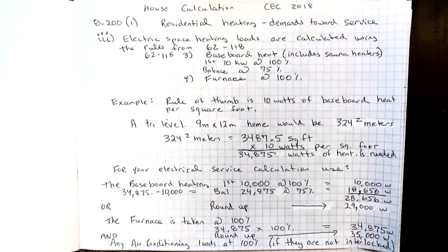Section 4 says that for a furnace, we have to take that as 100% towards our service calculation. That's because when the furnace comes on, it comes on all together, all at once.